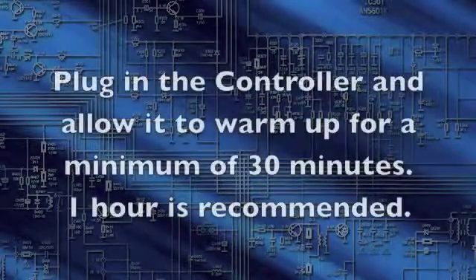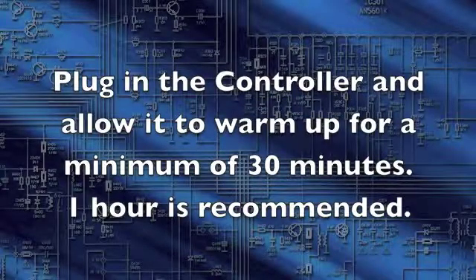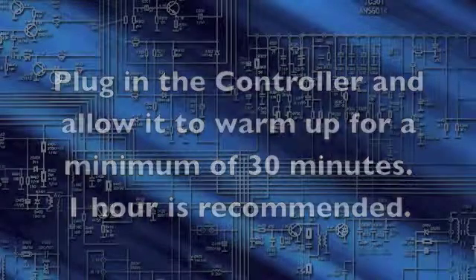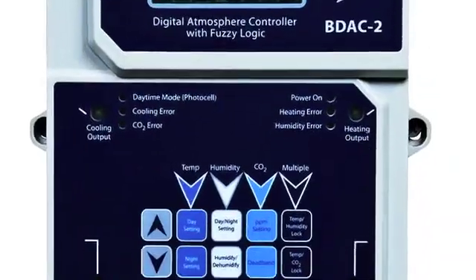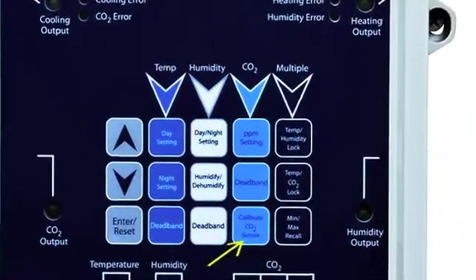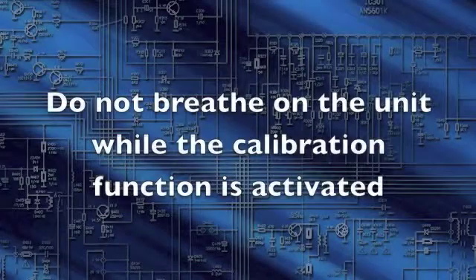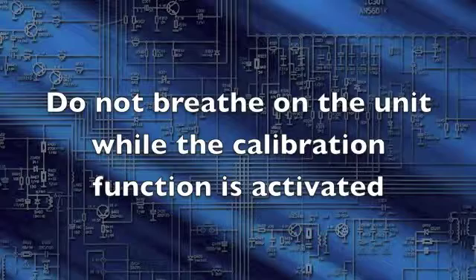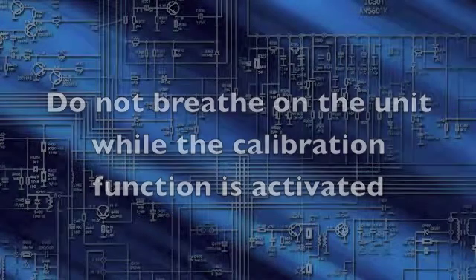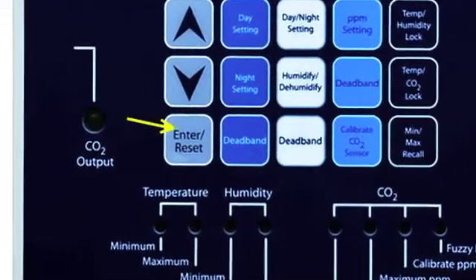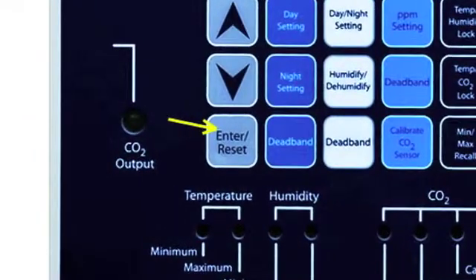Plug in the controller and allow it to warm up for a minimum of 30 minutes, but one hour or more is recommended for optimal calibration. Press the Calibrate Sensor button to activate automatic calibration. Do not breathe on the unit while the calibration function is activated. Press Enter Reset to start the calibration sequence.